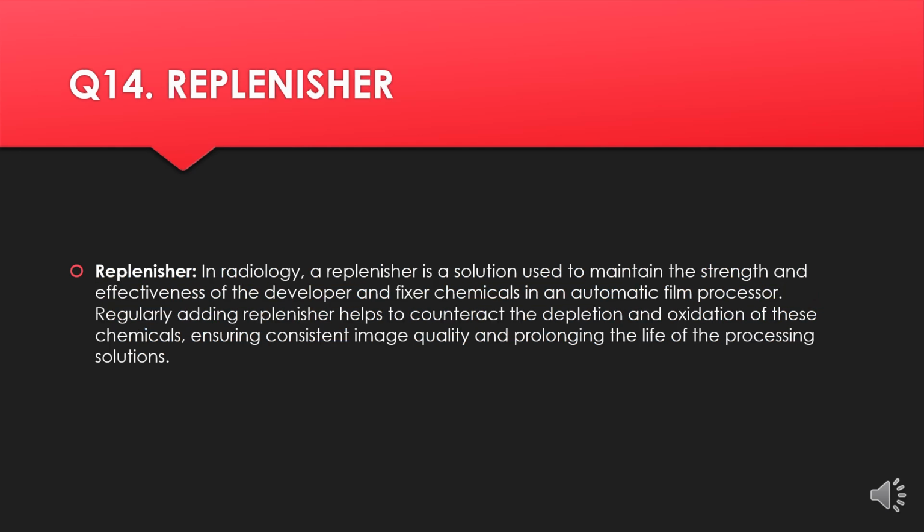Replenisher. In radiology, a replenisher is a solution used to maintain the strength and effectiveness of the developer and fixer chemicals. Regularly adding replenisher helps to counteract the depletion and oxidation of these chemicals, ensuring consistent image quality and prolonging the life of the processing solutions.